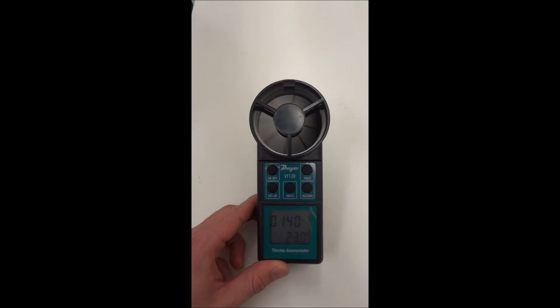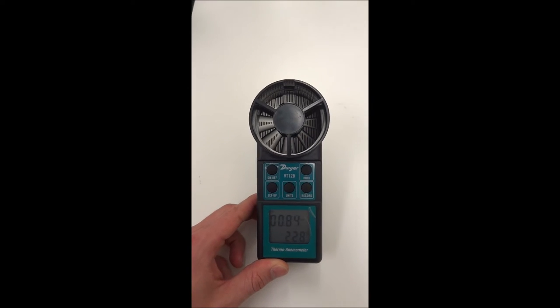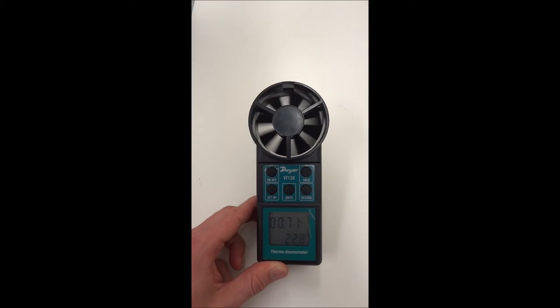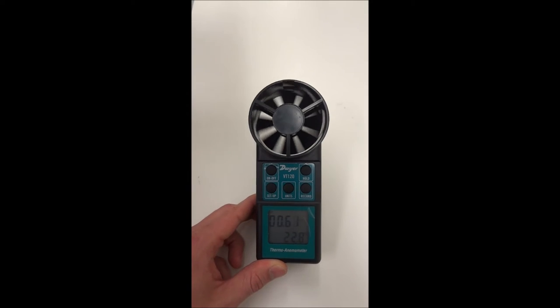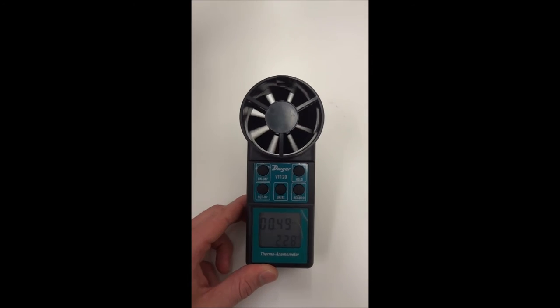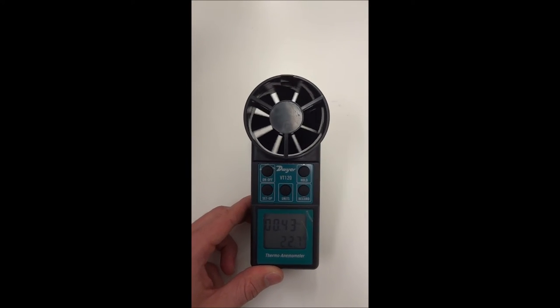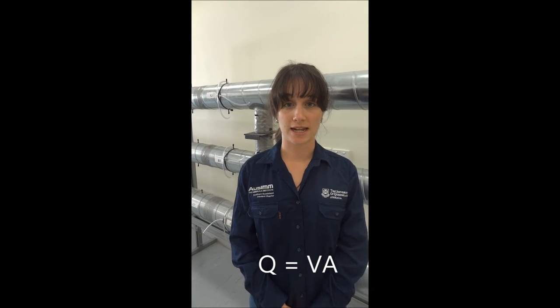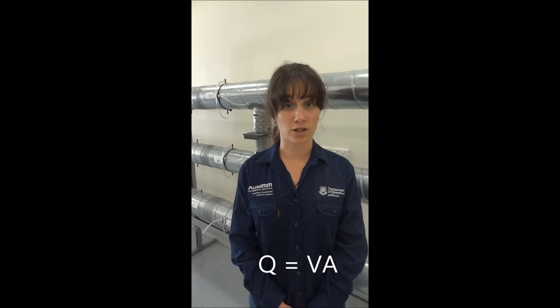The final method is by using a vane anemometer. It works by airflow rotating the blades in the fan, and a gearing and clutch system inside allows the velocity and temperature of the air to be calculated and displayed on the screen to within an accuracy of about five percent. Quantity is the product of velocity and area, so by calculating the velocity and measuring the area of the duct we can calculate the airflow through the tube. The temperature will be used to calculate the density of air from the ideal gas law.